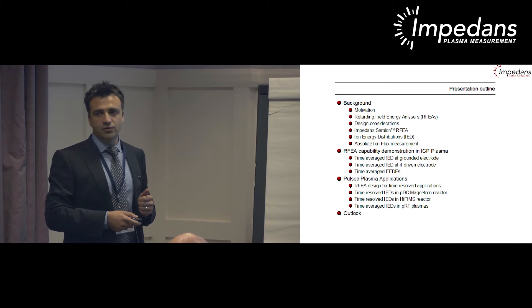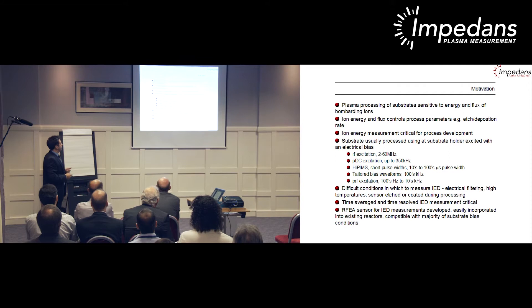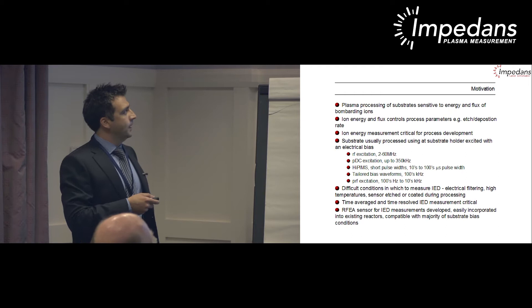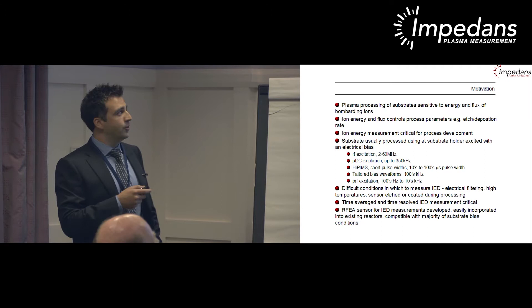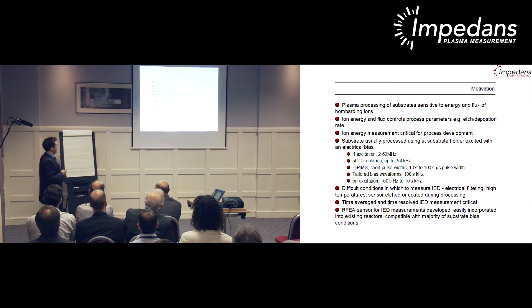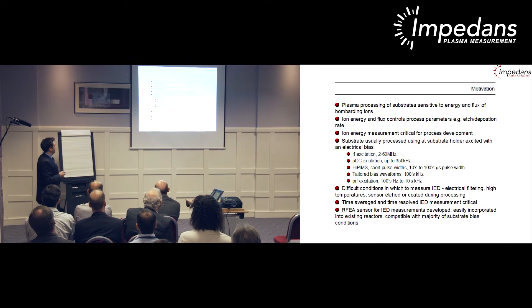The motivation: plasma processing of substrates is very sensitive to the energy and flux of bombarding ions, which control important parameters such as etch or deposition rates. Ion energy measurement has become critical for process development, especially as feature sizes become more complex. Substrates are usually processed using electrical bias, which complicates the measurement—this can be RF bias, typically in the 2 to 60 megahertz range and higher, or pulse DC excitation up to 350 kilohertz.